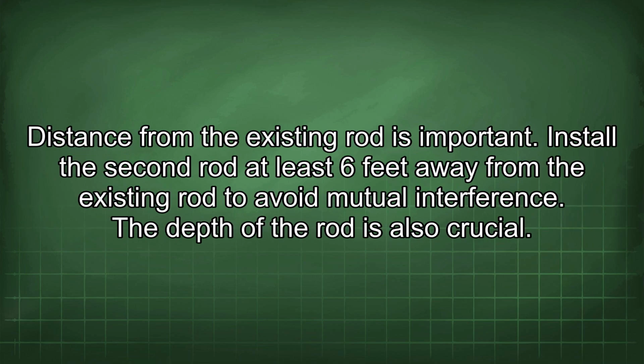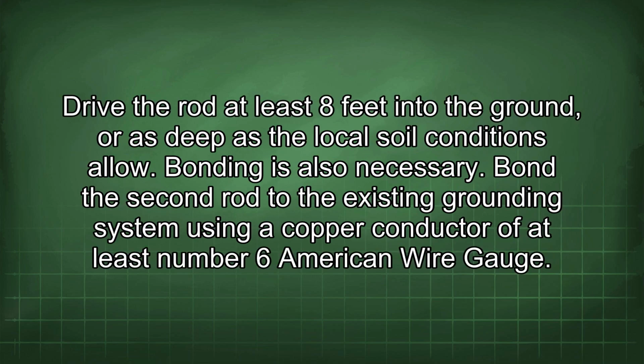Distance from the existing rod is important. Install the second rod at least 6 feet away from the existing rod to avoid mutual interference. The depth of the rod is also crucial. Drive the rod at least 8 feet into the ground, or as deep as the local soil conditions allow. Bonding is also necessary. Bond the second rod to the existing grounding system using a copper conductor of at least number 6 American wire gauge.